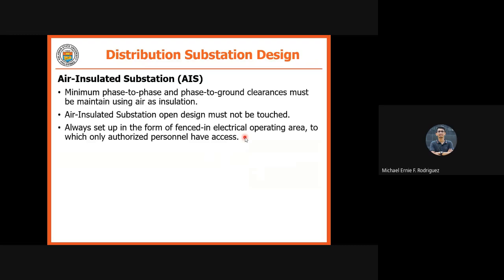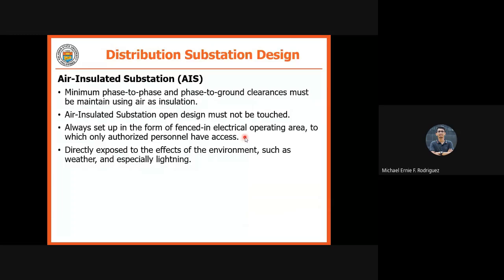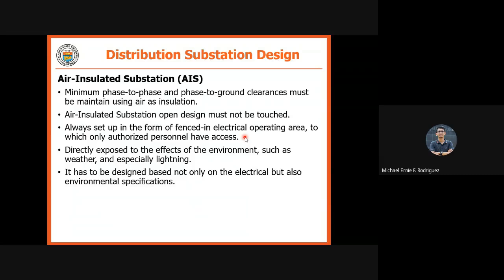And then, it is always set up in the form of a fenced-in electrical operating area to which only authorized personnel have access, like we said earlier. So, AIS is directly exposed to the effects of the environment, such as weather, especially lightning. So your substation can be hit by lightning if it is AIS. So there is a chance. I think it has happened before that a substation here was hit by lightning. I am not sure if it was the Paleco or the Irawan substation that was hit. Anyway, it happened once that the substation was hit, and as a result, there was a blackout. It has to be designed based not only on electrical but also environmental specifications. This is important.